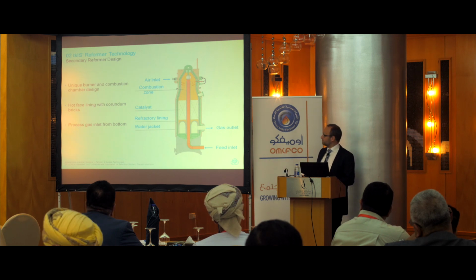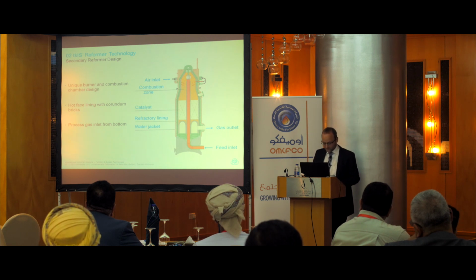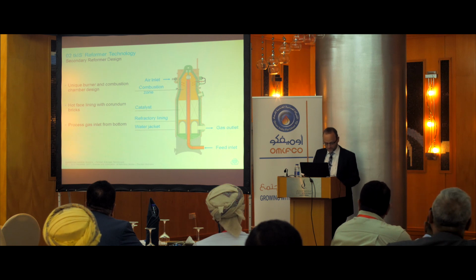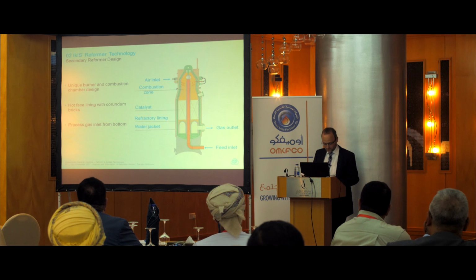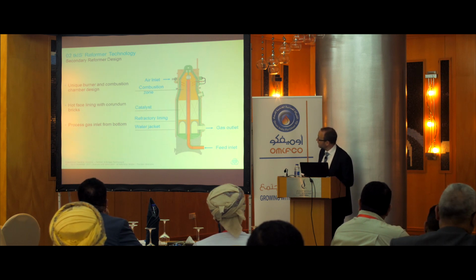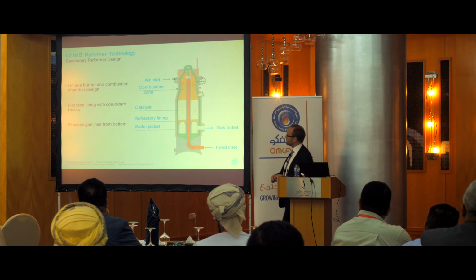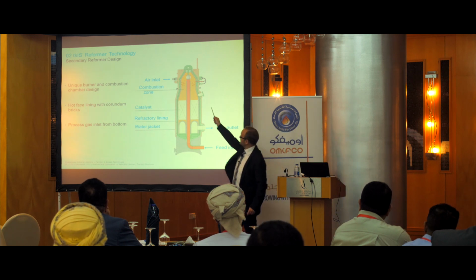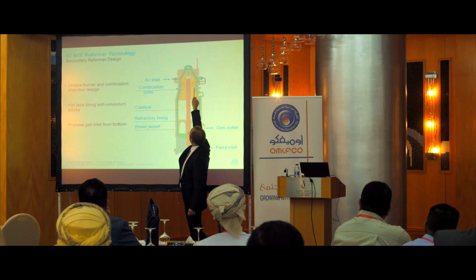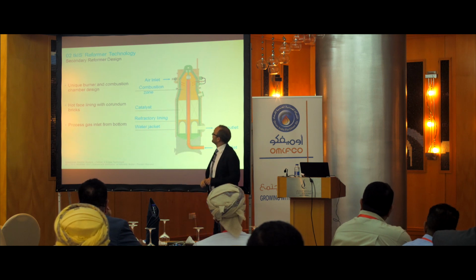The TKS burner design, which you can see here, is quite unique. We have an external distribution ring and multiple nozzles penetrating only slightly into the combustion zone. Thus, there are no metallic parts subject to the high temperature in that zone. Since the system was installed, we haven't had any failures of any burner here because we don't have any metallic parts in this area anymore.